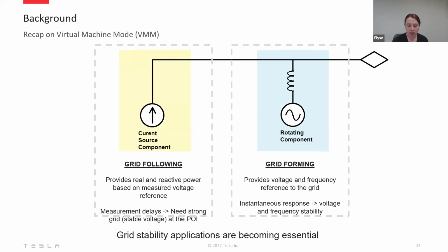I know some of this has been covered in previous ARENA presentations, but I think it's worth doing a recap of exactly what virtual machine mode is. Then I'll dive into more details of the actual Hornsdale project. This slide is intended as a schematic representation of how the inverter works. The picture in yellow on the left represents a standard architecture for an inverter-based generator. It's really a current source that provides real and reactive power in response to direct commands or in response to market conditions and network health. On the right-hand side in the blue box is the machine or grid forming element. When operating in virtual machine mode, this grid forming element operates in parallel with the grid following one.